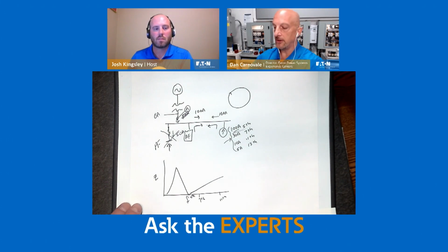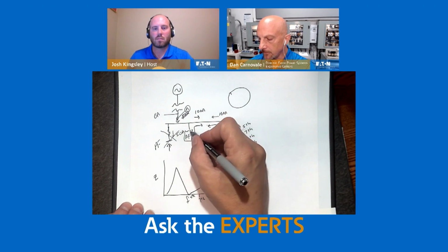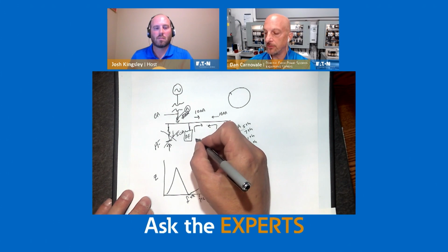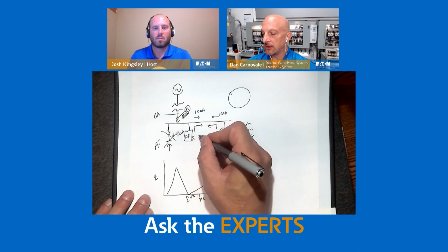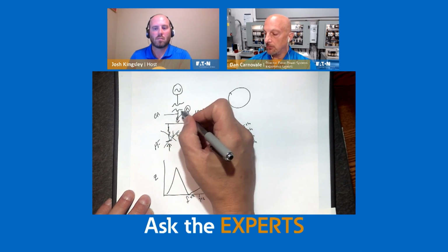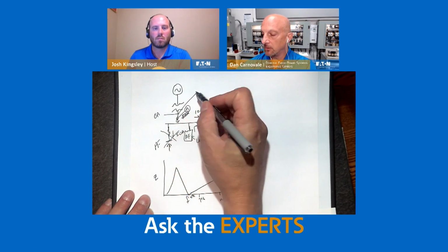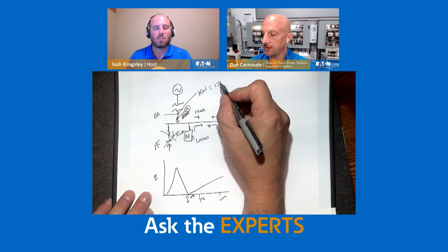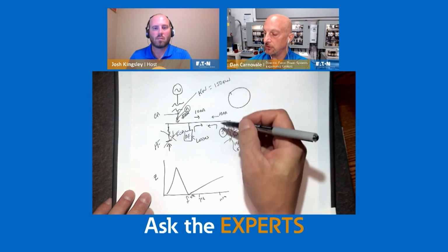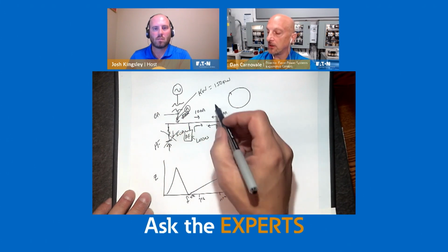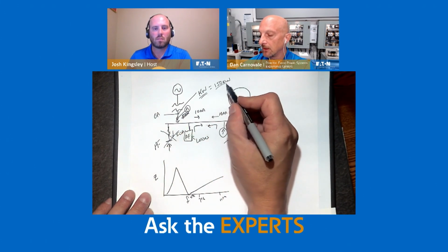But the other part of that, addressing losses, is what does this thing do? It injects current. And the way it injects current is through a power converter. And this thing has losses. So let's say you measure, not current up here, but power, kilowatts. And let's say your load was 150 kilowatts. You have all your harmonic current on there, and you turn off your active filter at 150 kilowatts. And then you turn on your active filter. Your kilowatts actually will go up a little bit.